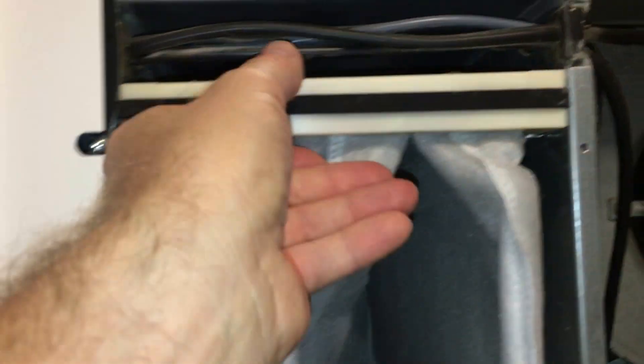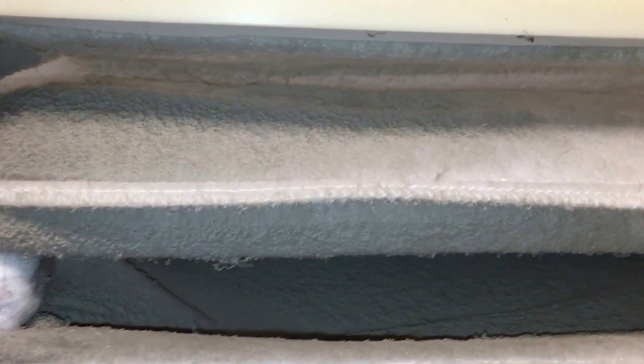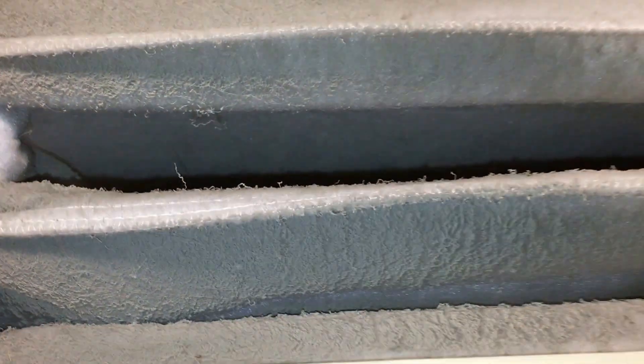This is the new filter that's going to go back in to replace it today. And this is the exit air filter, which is also filtered before it goes through the heat exchanger. As you can see, that is much, much cleaner — even though it's been through the house and coming back out, it's just effectively grey and sort of house dust.